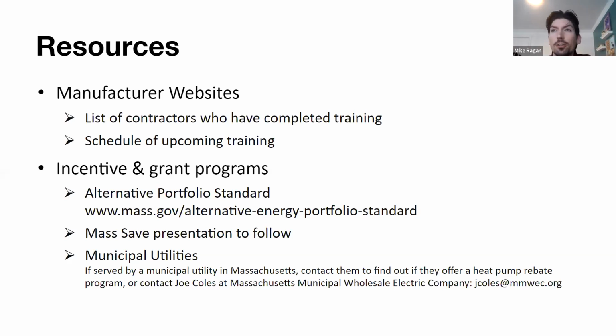So from a dollar amount standpoint, if someone says, I paid $300 for my electric bills this month, if that was electric resistance, where you're only getting a COP of 1, and that $300 was instead spent on a heat pump, you're getting twice as much heating output. And ultimately, that's where the ROI comes from. It comes from that ability to more efficiently use electricity for that space in order to provide that heating.